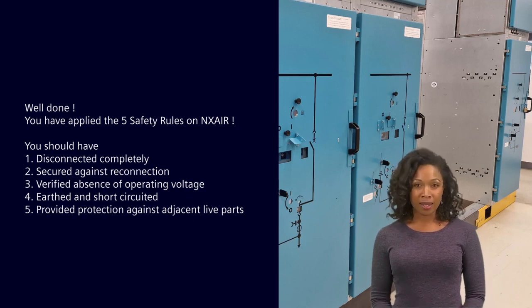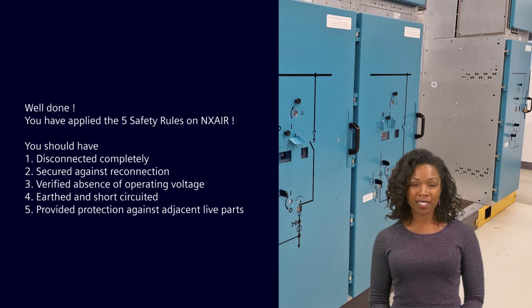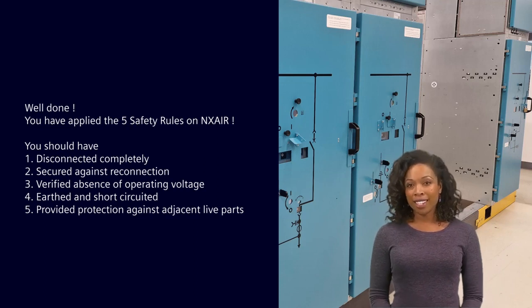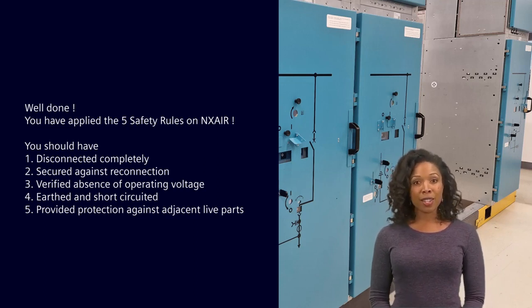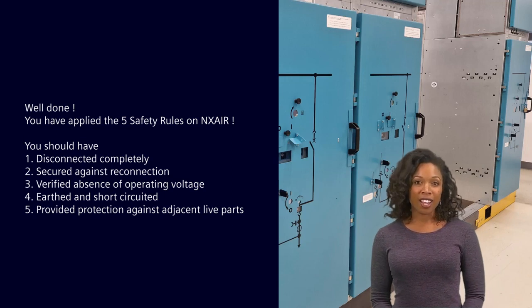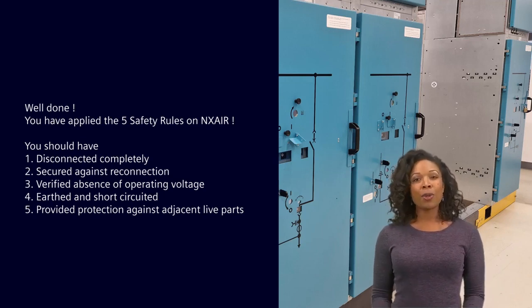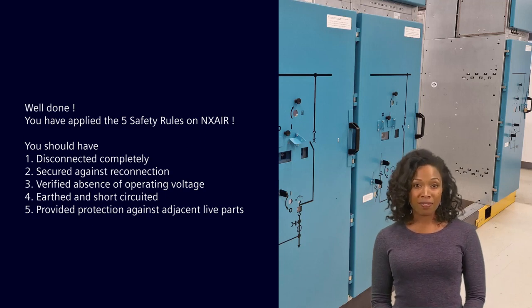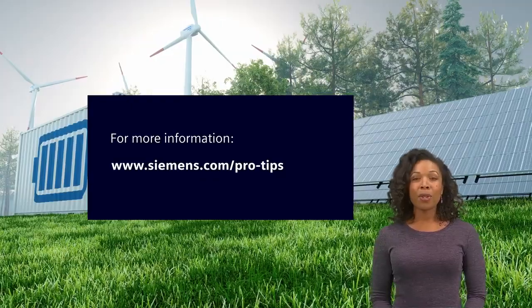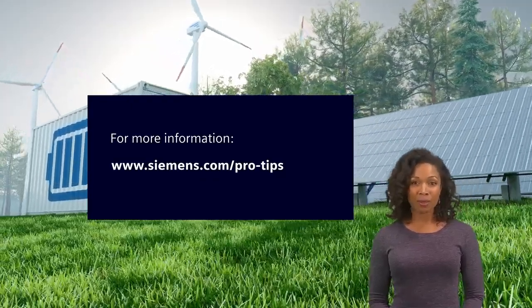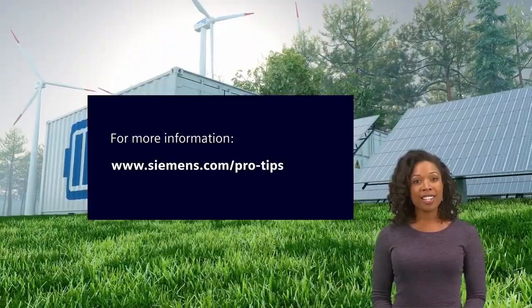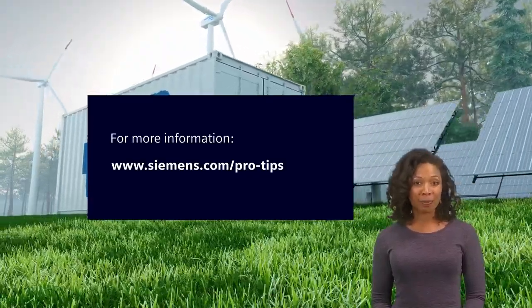Until verified, all electrical sources are assumed to be energized. Step 1: Disconnect completely. Step 2: Secure against reconnection. Step 3: Verify absence of operating voltage. Step 4: Earth and short circuit. Step 5: Provide protection against adjacent live parts. If you enjoyed this video, please visit the Siemens ProTips website and sign up to receive more useful tips from our experts.